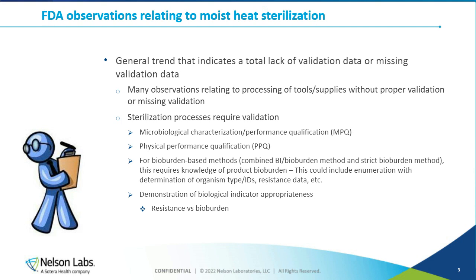There also were many observations relating to processing of tools, supplies, equipment that's used as part of the manufacturing process where proper validation had not been performed for those processes. So I think it's worth mentioning that when you are using a sterilization process in your manufacturing or as a terminal sterilization step, those processes need to be validated. Some of the things that you'll have to go through and are outlined in those documents that I mentioned and other applicable documents relate to microbiological characterization and performance qualification. You'll hear that often referred to as MPQ. Physical performance qualification, PPQ.